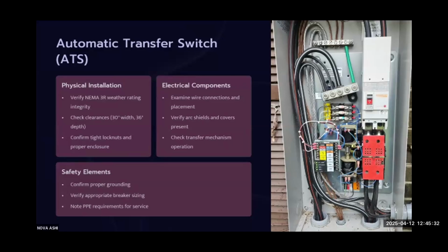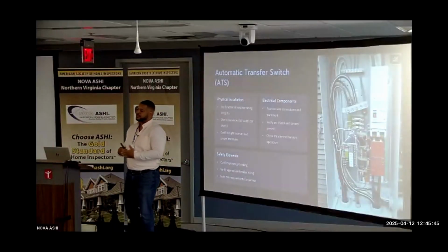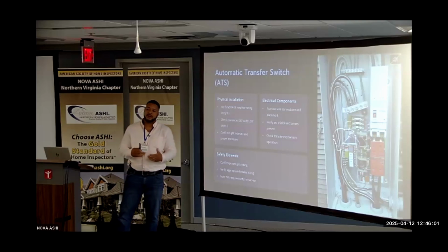For example, your service feed coming from the meter comes into this ATS and it goes through this transfer and it's all contacted. So these wires, we have 200 amp capability. We have an ampacity of 200 amps. But if it gets loose, we get a little resistance. Instead of being able to carry 200 amps, we may be only able to carry 100 amps. Now you start having some heating taking place, and it starts charring, and now you actually have resistance. Next thing you know, you're going to have possibly some burning, a possible electrical condition. You're going to lose power in the house, and the homeowner is going to be without power. So keep that in mind.